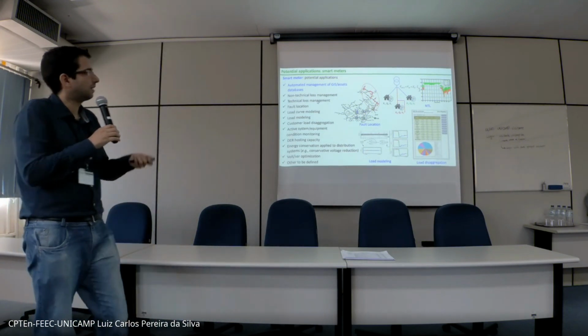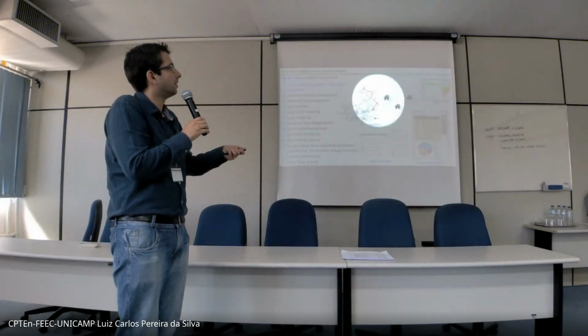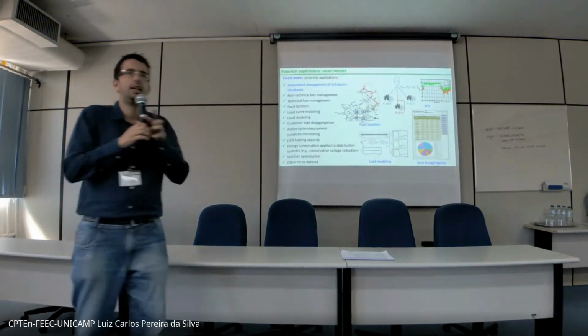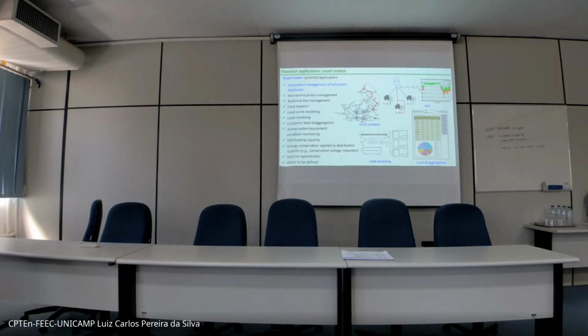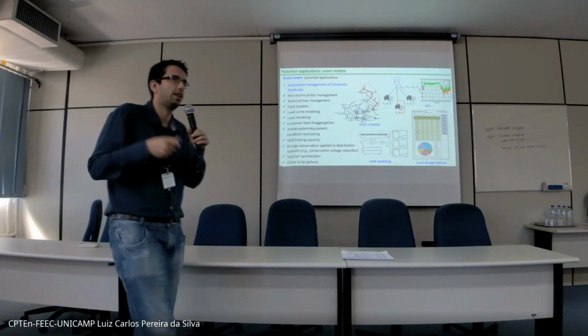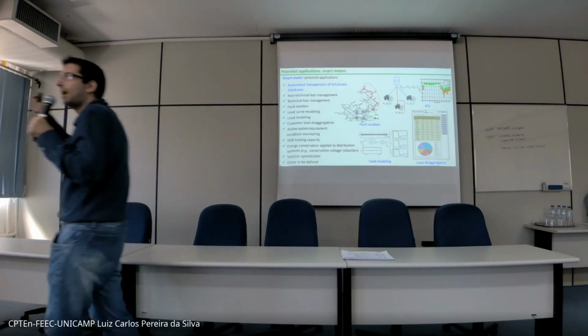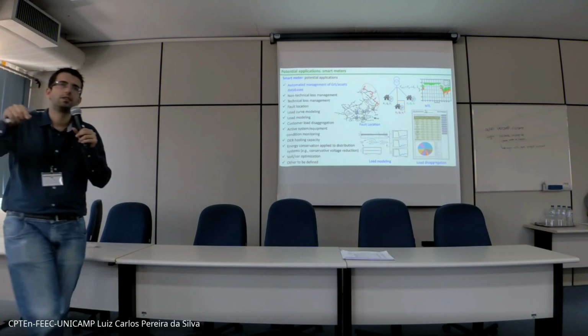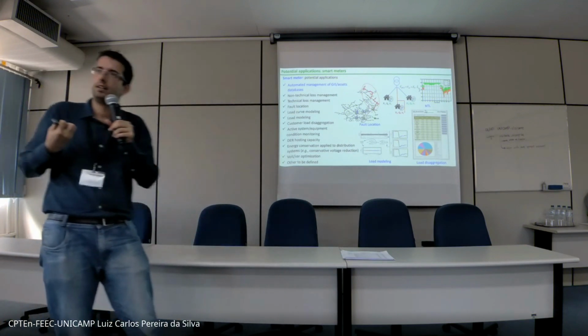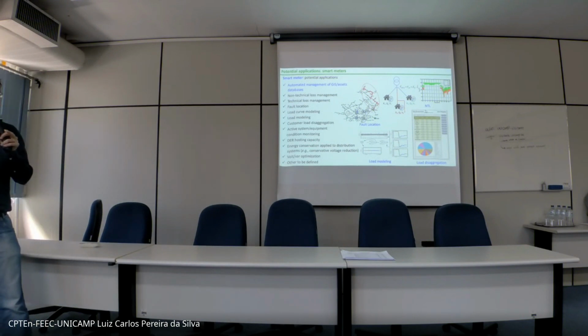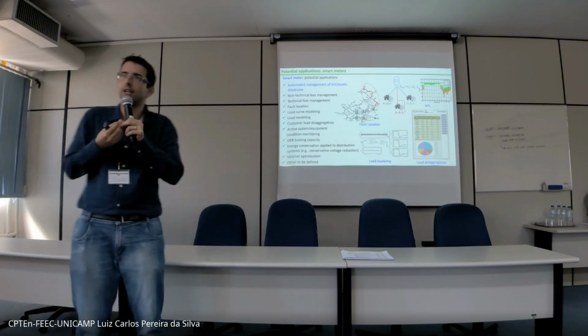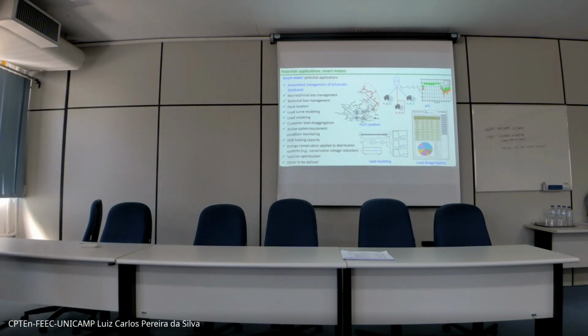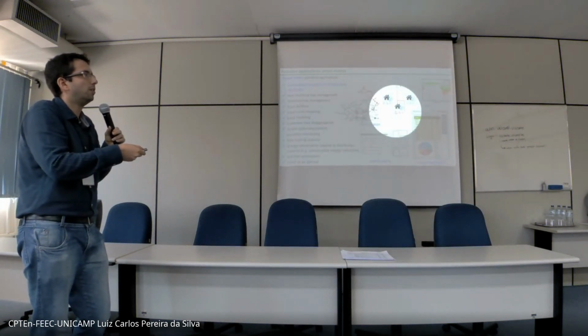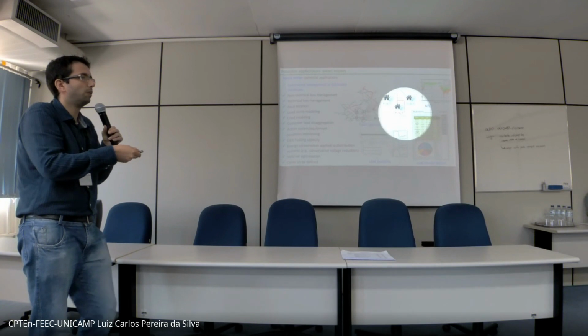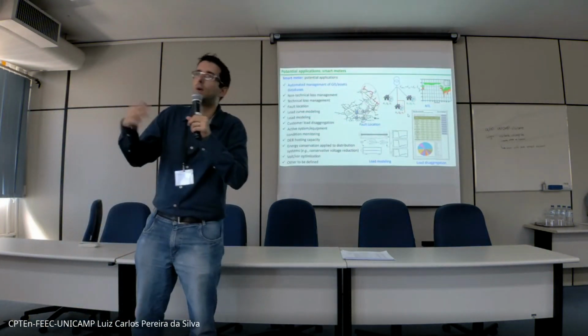For example, non-technical loss detection. This is about a project we conducted with BC Hydro in British Columbia, Canada, to detect non-technical losses using smart meters installed on low voltage customers. You extract this data and process it properly, and you can identify non-technical losses using active and reactive power and voltage measurements with 15-minute or 1-hour resolution.